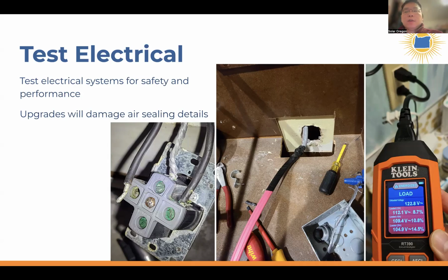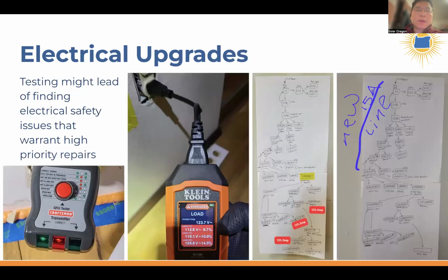A really good test for electrical is to do a load test. There are tools that can do load testing on outlets. What this load tester does is, for a fraction of a second, it puts like a 12 amp load, or a 20 amp load, on this receptacle, and then it measures the voltage drop while the load is on. And if you have a receptacle wire run that's very long, you will end up having a very high voltage drop, and you can end up having appliances that don't work properly, or overheat the wires in the wall if you plug in something that uses a large load, like a space heater, for example. And this is what we found in this home. The right two photos show the circuit map for one circuit. There were like 40 items, receptacles daisy chained onto one circuit.